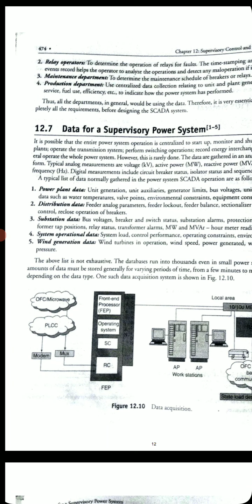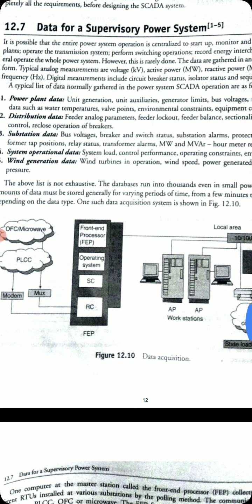You can see in this figure, one computer at the master station is there, that is called FEP. FEP is nothing but front end processor. This front end processor collects the data from different RTUs installed in the various substations by polling method. The communication method may be dial-up telephone or PLC method, optical fiber communication, or microwave. So the FEP, or front end processor, formats the data and processes it, then transfers it to the host server.